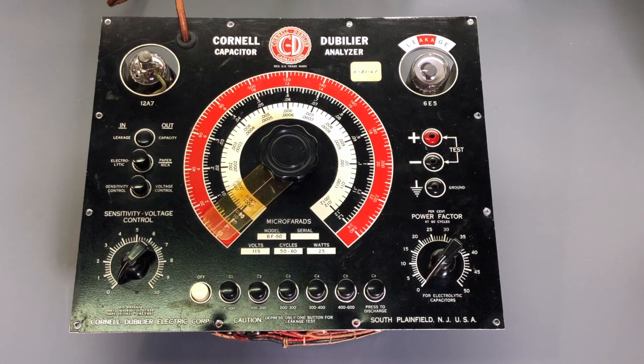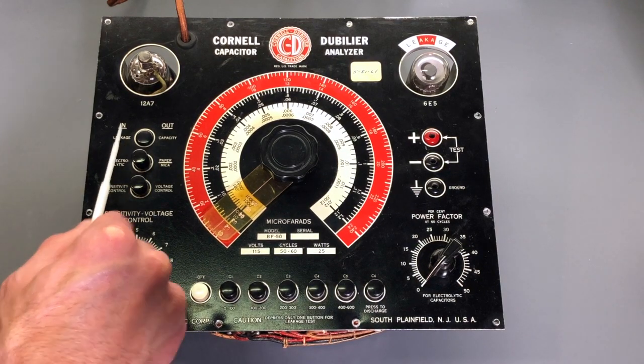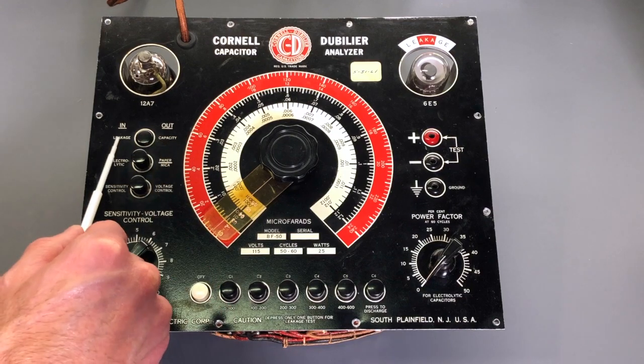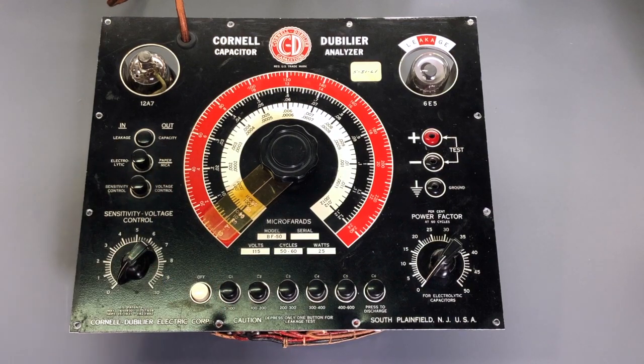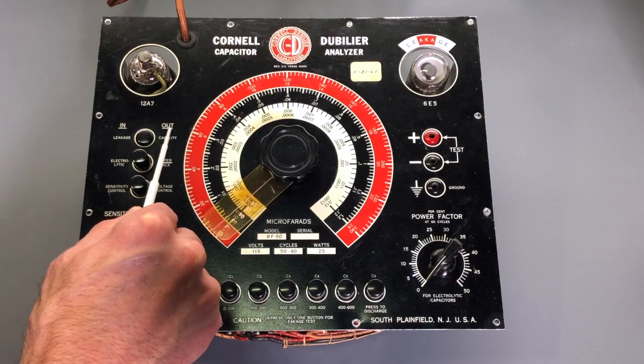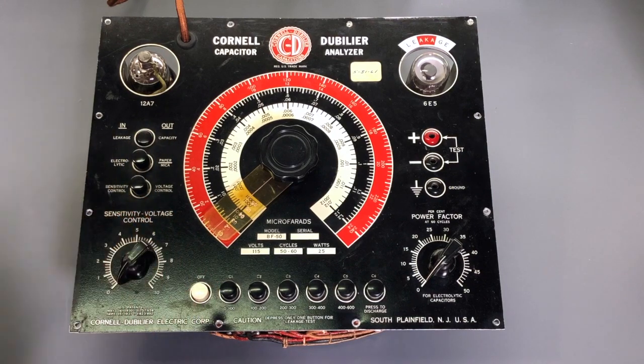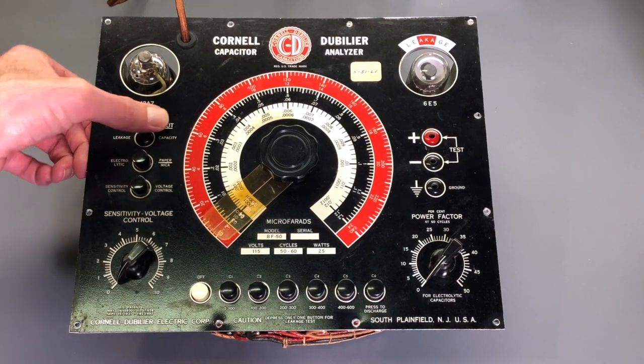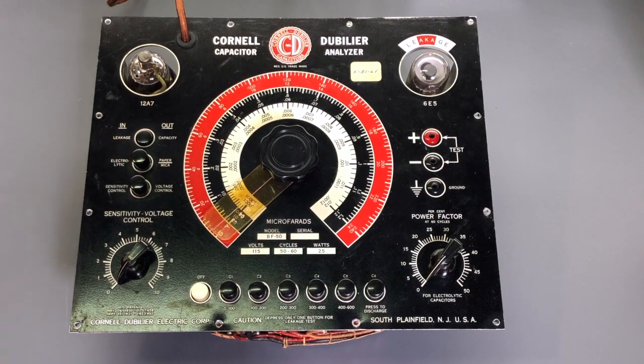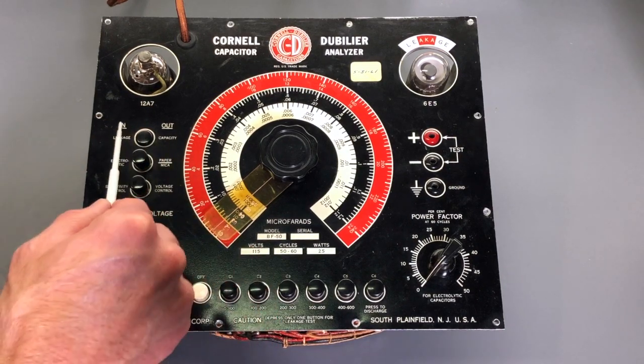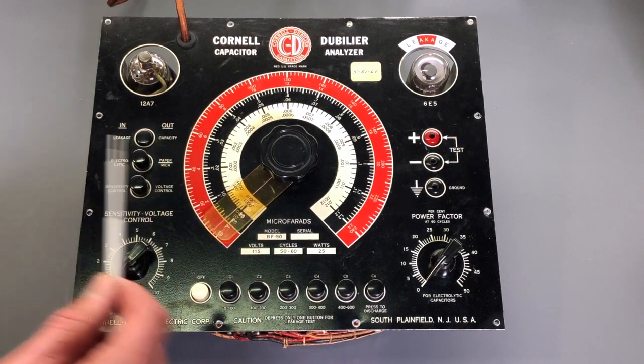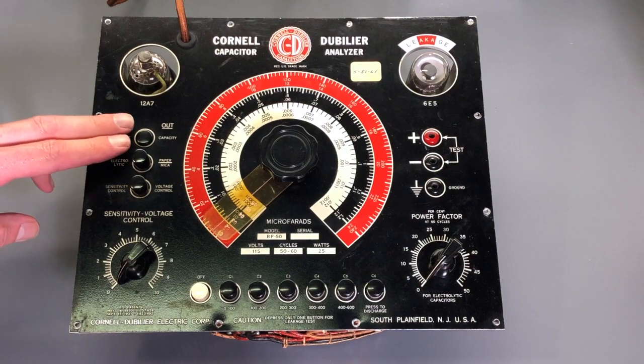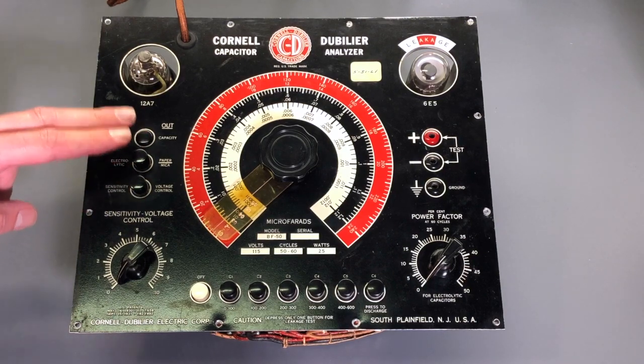Now, the tester has two basic functions. It has a leakage function and the capacity function. So we'll start with the leakage function first. Now, the in and out references on the switches refer to the switch being in or down, and out is up. So you can see the various combinations that you would select.